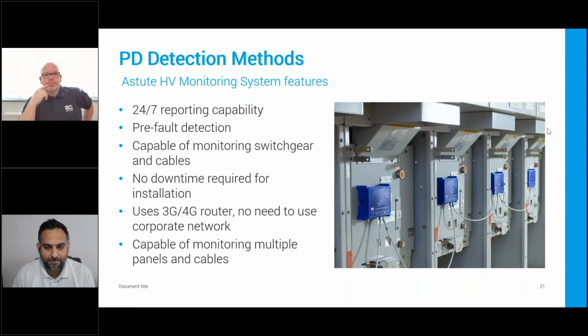Because it is a clever system, it captures the data, and you can set different types of alarms, and you can send those alarms via email or text messages to whoever the nominated people are, and that uses 3G, 4G communication to feed the data back to the cloud. And because it can monitor multiple panels, you can get a holistic picture of your whole switchgear board or cable assets as well. So it allows you to monitor and trend the activity, and you can see how, if there's any partial discharge activity, it's progressing across different components.